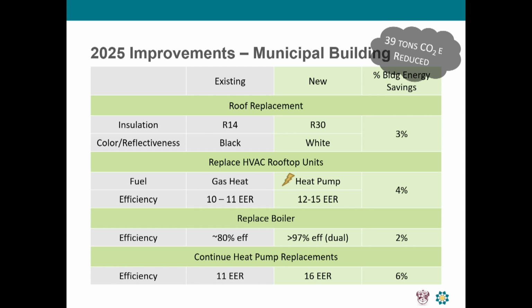So even though we're continuing to burn gas and have some CO2 emissions, you're substantially reducing CO2 emissions by going to the more efficient boiler, and also by providing water temperatures to our heat pumps that allow them to run at their peak efficiency. We can do better. I think if you compare it to a geothermal loop, probably the geothermal would use a little bit less energy. But there's so many other factors involved with designing geothermal that it didn't make sense for this building.